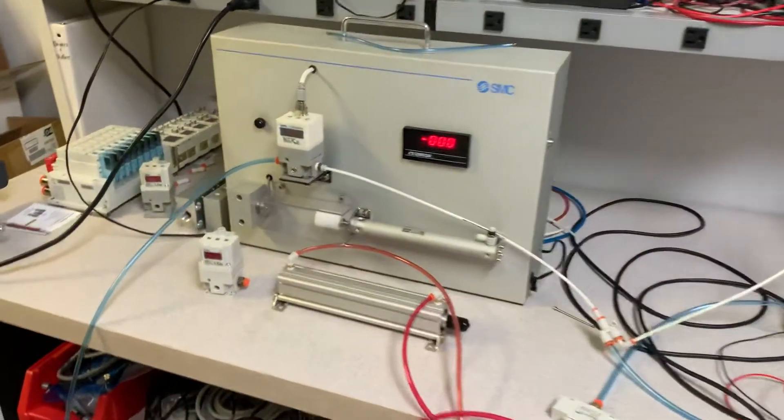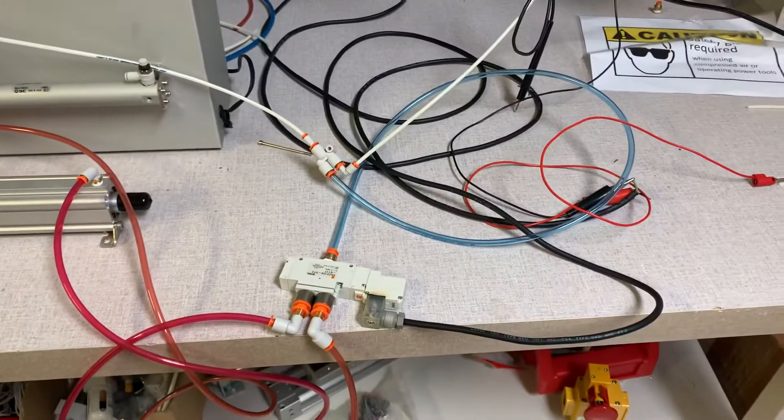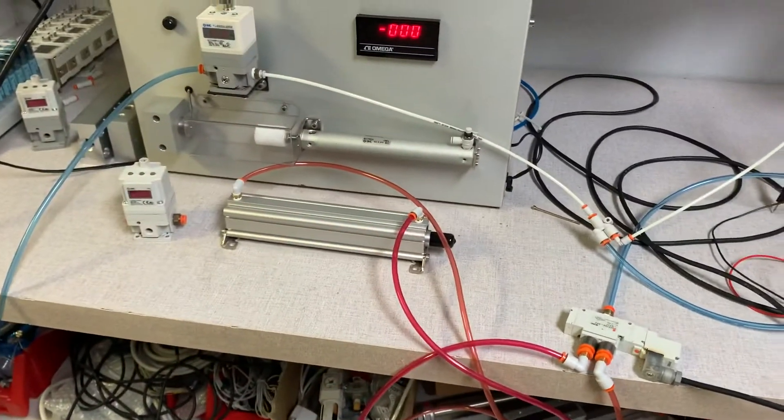The power is cut, no power to the ITV. The solenoid valve is de-energized, cylinder retracts.